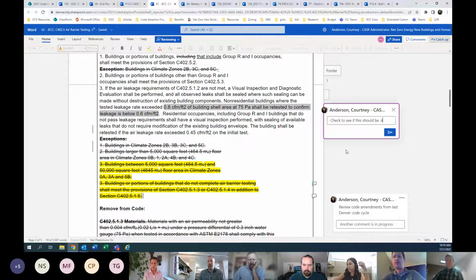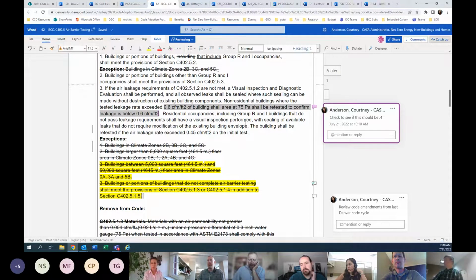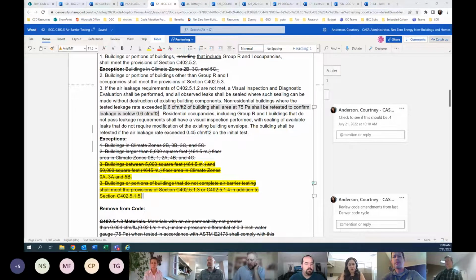Good. I'll just finish by saying what Sean had stated. I could be comfortable voting on it in our next committee meeting if it was 0.4 as a minimum, giving latitude that if you fail, you must at least bring it to 0.6. There will be scenarios where a building will have an extremely hard time even getting to that, but the building department unfortunately gets to cross that bridge when it comes up. As written, it should be saying do everything in your power to get to 0.4.